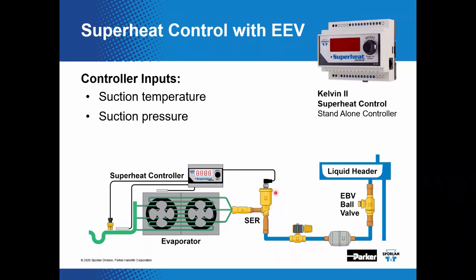Upon powering up the controller, the installer is prompted for system information such as, here's a good one, number of EEV steps. Why is that important, Glenn? Well, because not every valve out there has the same number of steps, and therefore our controller needs to know which one it is and how many steps so it can tell it exactly where to go and when to go. Well, at least respectfully anyway. Yes. Okay. Refrigerant type. Why is refrigerant type important? Because not all refrigerants have the same pressures at the same temperatures, and therefore it needs to know that in order to calculate superheat properly.